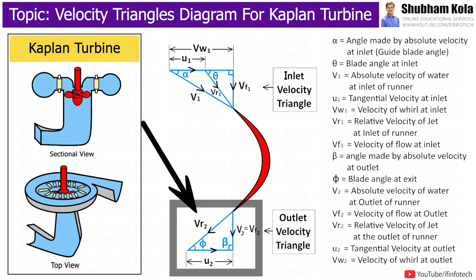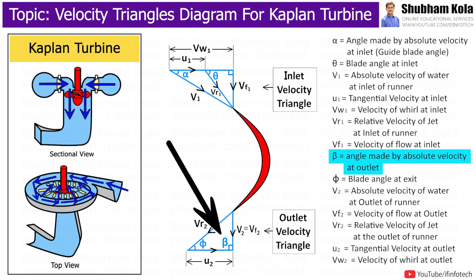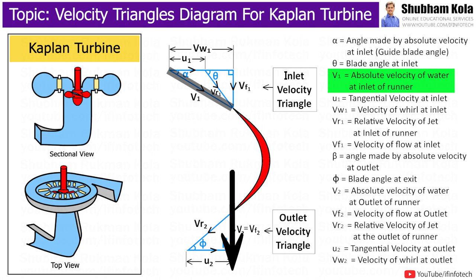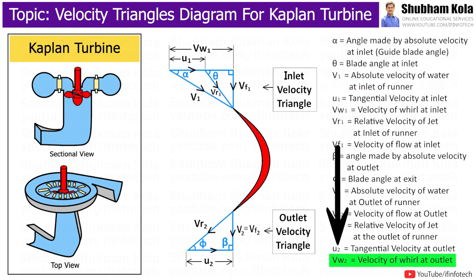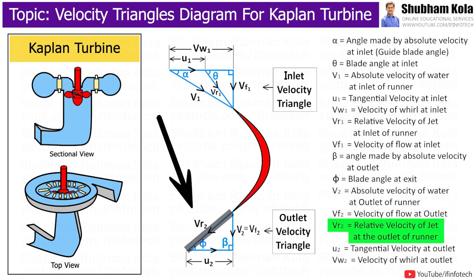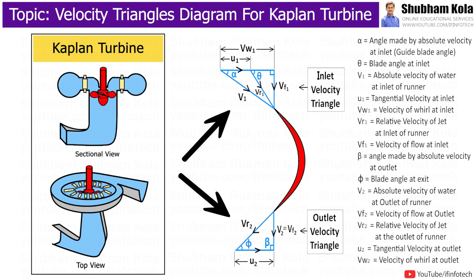Now we will draw the outlet velocity triangle for Kaplan turbine. In Kaplan turbine, water comes out in the axial direction, meaning the outlet angle β is 90 degrees. When β is 90 degrees, the velocity of water at outlet V2 is vertical, the horizontal part Vw2 is zero, so V2 equals Vf2 and Vw2 is zero. The relative velocity at outlet is Vr2, making angle φ with the horizontal, and U2 is the blade velocity at outlet. This completes the velocity triangle diagram for Kaplan turbine.